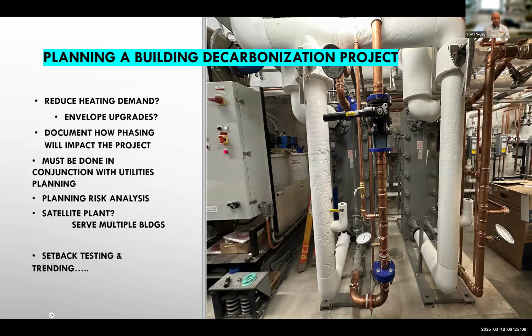Satellite plants. We sometimes build a kit like we just saw in the previous slide to do multiple buildings. Groups of maybe 2 or 3 that are then sub-metered, but they're close enough to run secondary piping, which can be plastic, to feed those systems. So you save all kinds of money on heat exchangers and controls for the primary production kit. You have to consider, well, utilities planning for a district system. Consider building one low temperature hot water production plant that can serve multiple buildings. That's the satellite plant if they're close by.